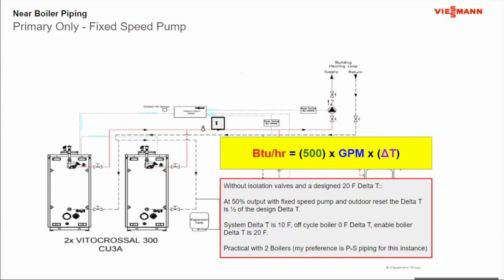So I'll work easy numbers. Let's say my inside temperature is supposed to be 70 degrees Fahrenheit. My outside temperature is 0 degrees Fahrenheit. That gives me a 70-degree delta T. On the 0-degree day, I expect both boilers to run. On a 35-degree day, the load on the system is going to be half of the design load. So half the design load, my control should only be running a single boiler.